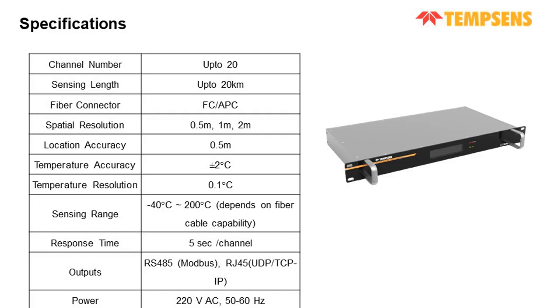The fiber connectors are FC APC type. The spatial resolution is defined as the amount of fiber to be heated to get an accurate reading, so it ranges from 0.5 meter to 2 meter. Then the location accuracy is 0.5 meter. Temperature accuracy is plus minus 2 degrees centigrade with a resolution of 0.1 degree centigrade. The sensing range, which is dependent upon the fiber itself, varies from minus 40 to 200 degrees centigrade. And the response time is 5 seconds per channel.